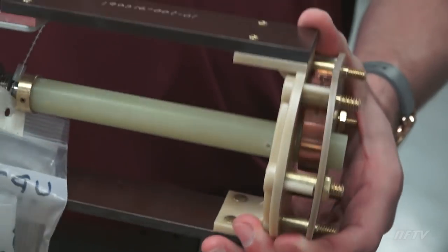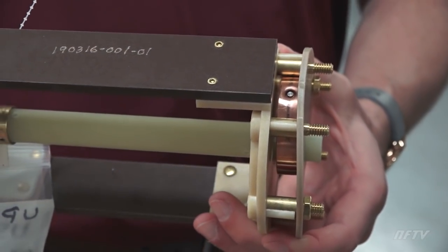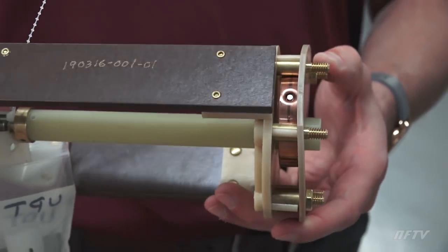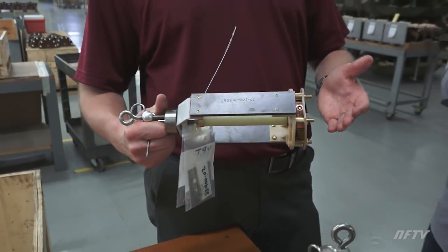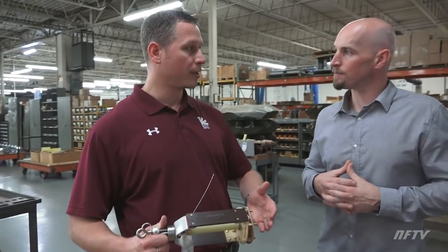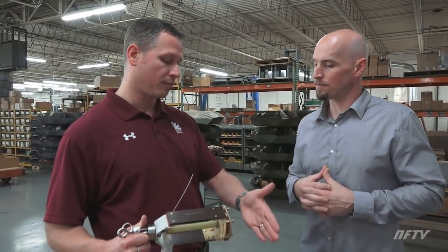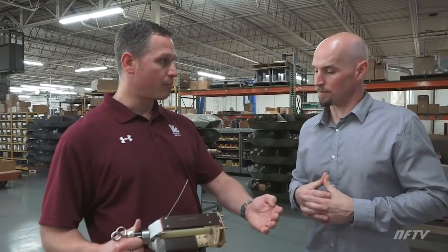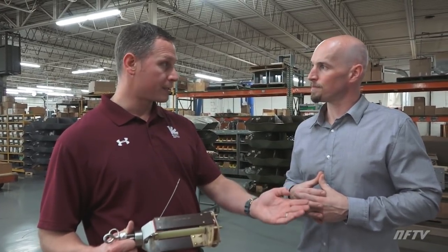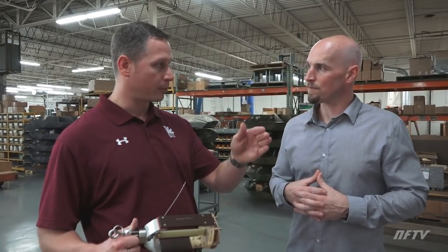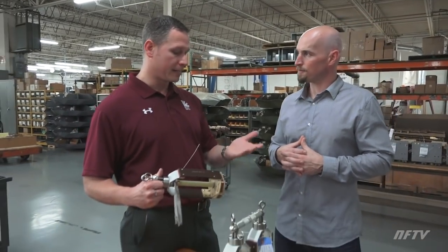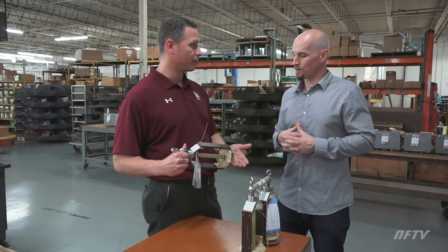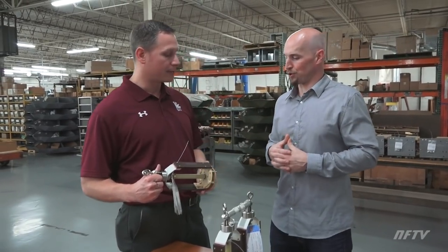So is there a particular time when they would do that? What would be an instance where someone would have to do something like that? For example, if a transformer was used in a housing development that started with 3 houses, and it was installed and set at a certain voltage output, then 4 more houses were built, there's going to be a voltage sag. So they may want to adjust the voltage output up a little bit. Instead of bringing in a complete new transformer, they adjust the taps to give maybe 5% more output. This switch allows them to do that.